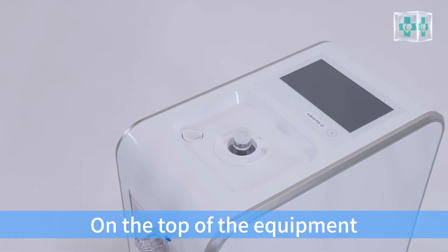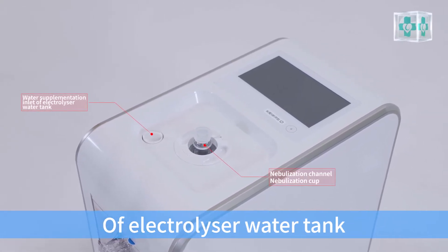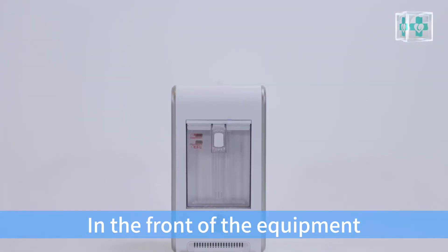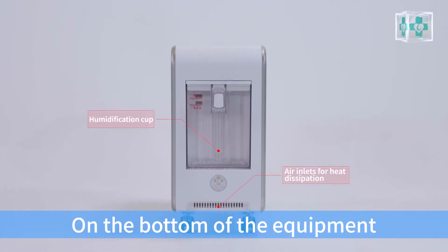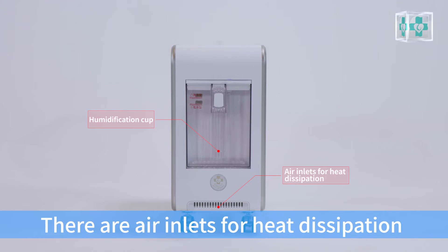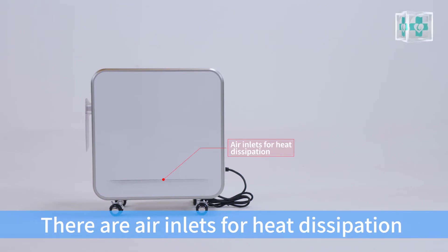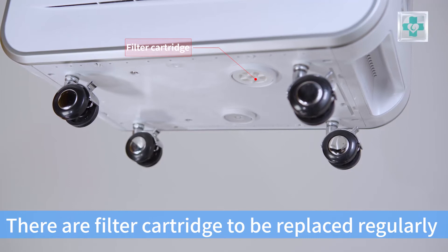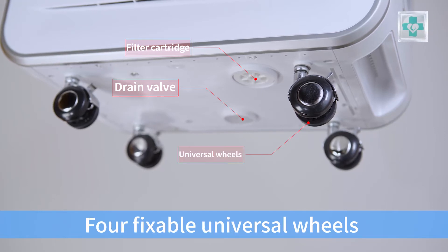On the top of the equipment, there is a humidification cup containing hydrogen water. On the bottom of the equipment, there are air inlets for heat dissipation. On both sides of the equipment, there are also air inlets for heat dissipation. At the lower part of the equipment, there are filter cartridges to be replaced regularly and a drain valve for regular washing of the equipment.